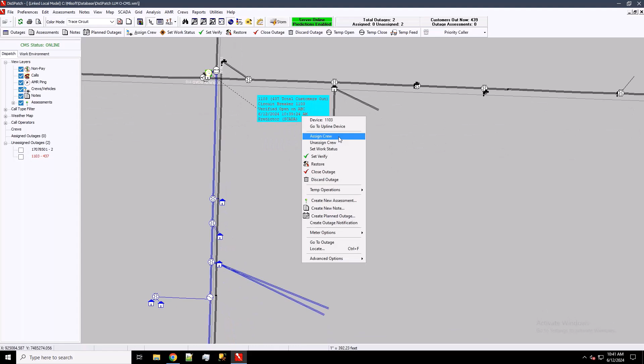The difference here is when the SCADA operation comes in, it is immediately a verified outage. We know from SCADA this device is locked open. We know we have all 437 customers downline from this outage out of power. So if I'm a dispatcher, that gives me great confidence - hey, we've got to get somebody out there.